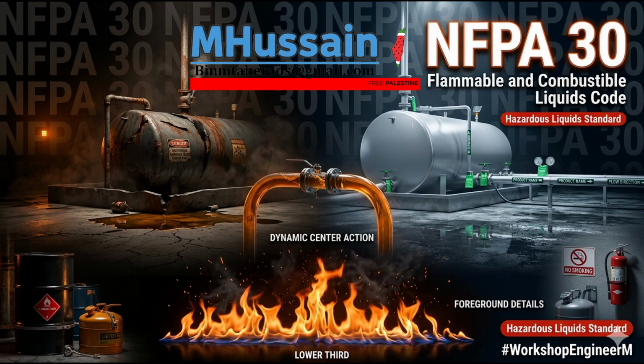Precisely. Also, the door has to have a robust 3-point latch. In a 1,500-degree fire, the steel will warp violently. A single latch would just pop right open. The 3-point latch holds it tight against the frame. Now, speaking of holding it tight, there's a totally counterintuitive rule in the text here. If I'm a safety officer looking at a sealed metal box of explosive chemicals, my first thought is, we need to ventilate this box so fumes don't build up. Naturally. But the code explicitly says storage cabinets are not required to be ventilated for fire protection. In fact, if you do ventilate them, you have to run highly specific fire-rated piping all the way outdoors.